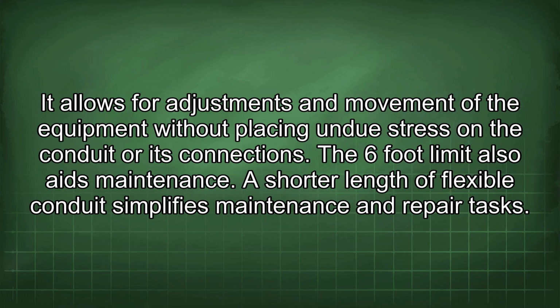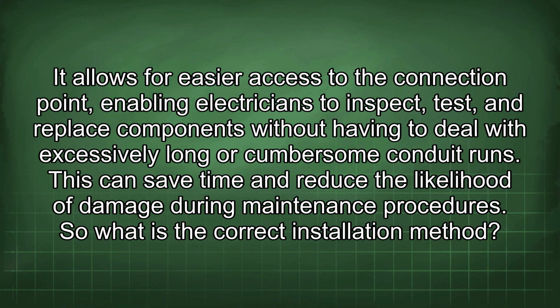The 6-foot limit also aids maintenance. A shorter length of flexible conduit simplifies maintenance and repair tasks. It allows for easier access to the connection point, enabling electricians to inspect, test, and replace components without having to deal with excessively long or cumbersome conduit runs. This can save time and reduce the likelihood of damage during maintenance procedures. So what is the correct installation method?